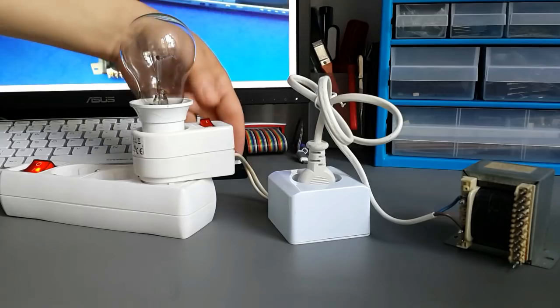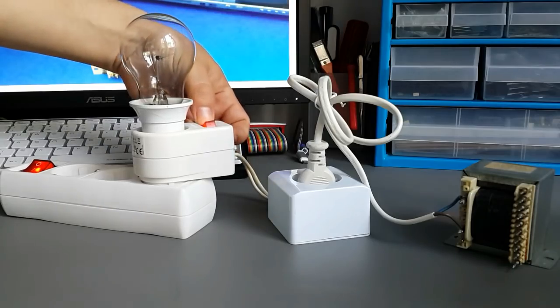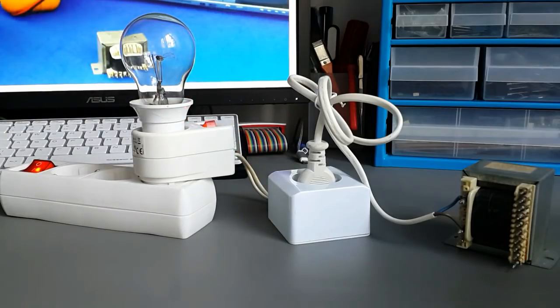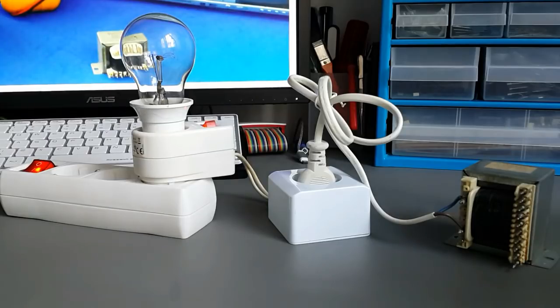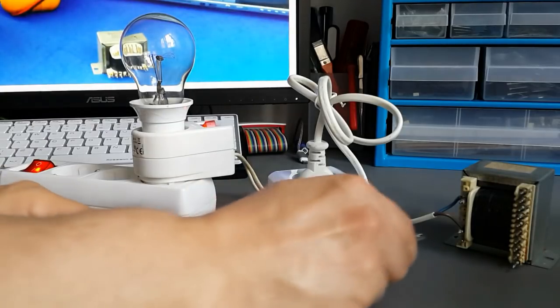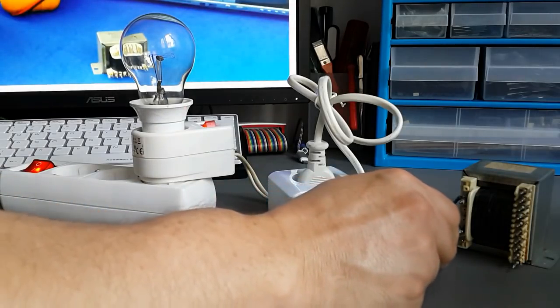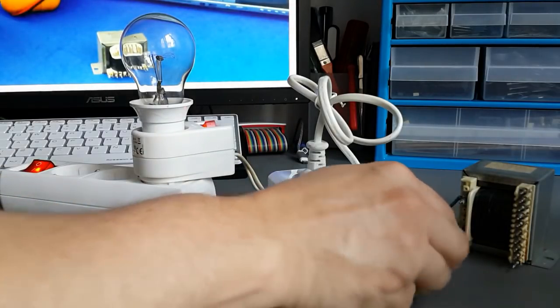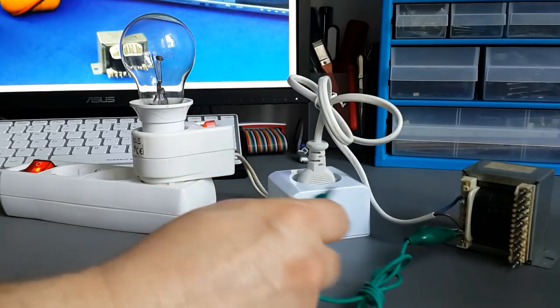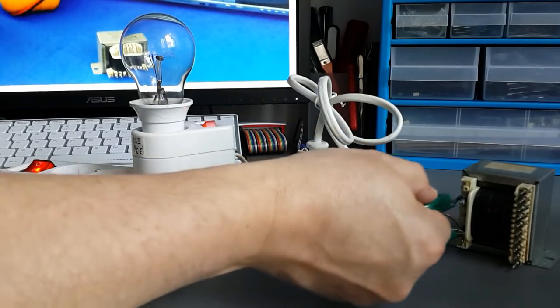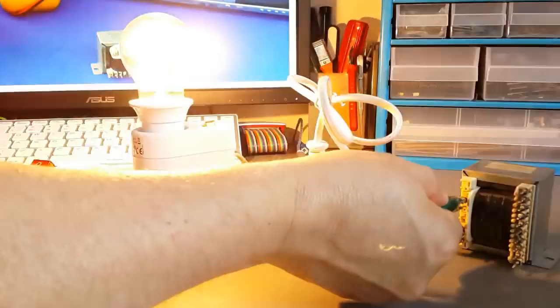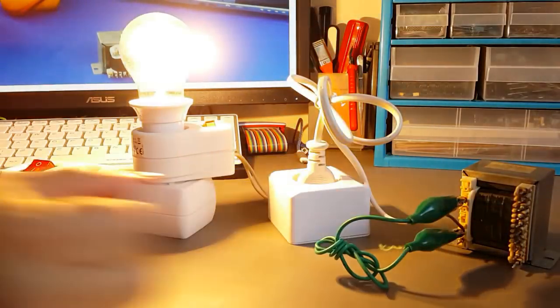We need to transfer 80-75% of the voltage to the device under test, the equipment we are trying to review or to test. 20%, 25% of the voltage will be on the lamp. If the device under test is in short circuit, all the voltage will be on the lamp, the light will be on and nothing else will happen.